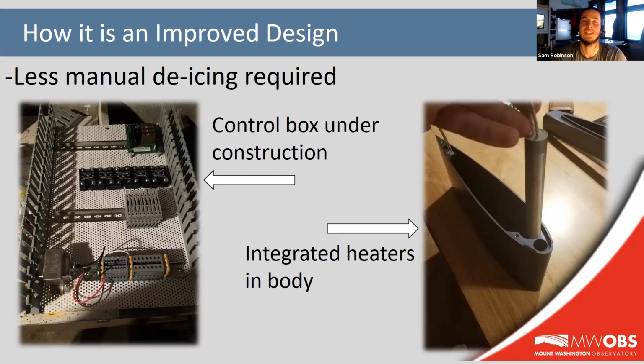I say almost because in rare cases, we do still have to go up and knock some ice off, but it usually only requires a slight vibration of the mounting post to knock off any of that accreted rime or glaze ice. In my experience with major icing events, I'm not really sure there's any heating system in existence that could realistically keep up. It does definitely get really crazy at times. And relative to Pitot 19 and our other previous anemometers, though, it definitely performs much better.